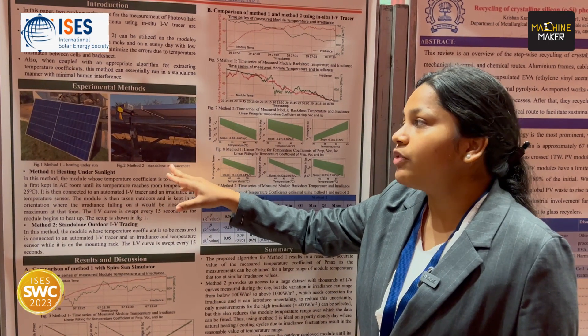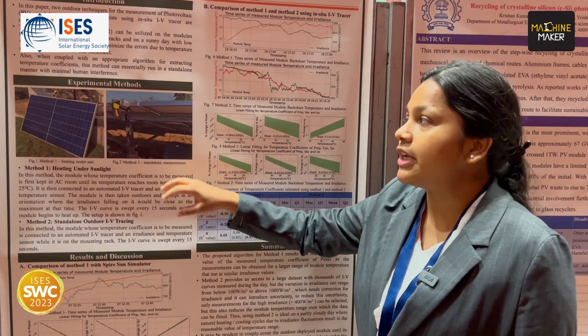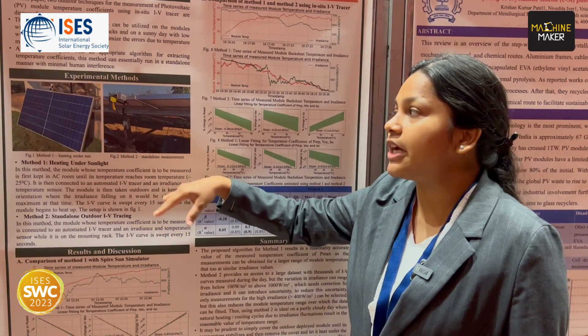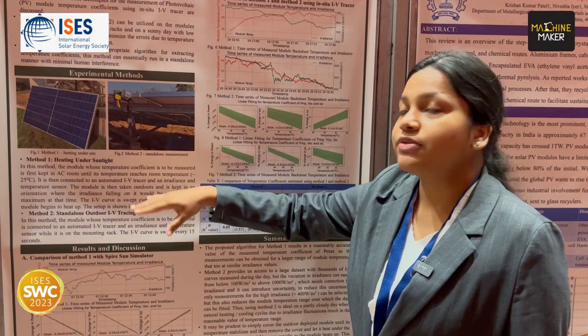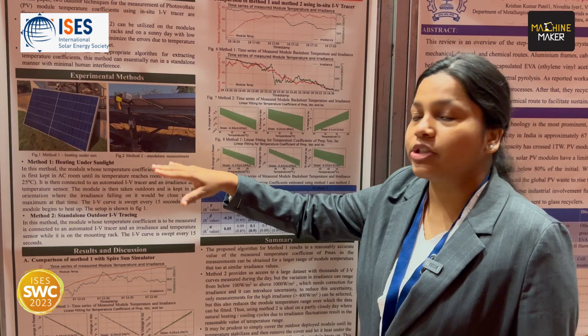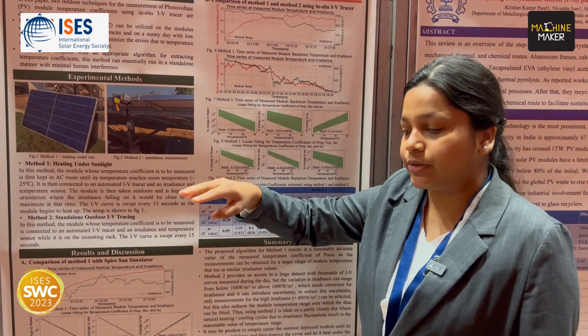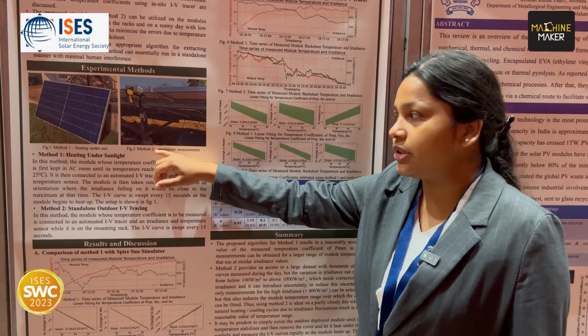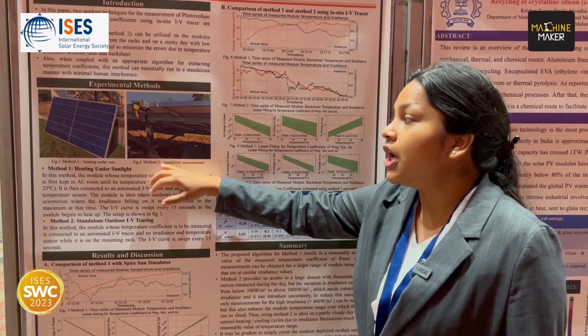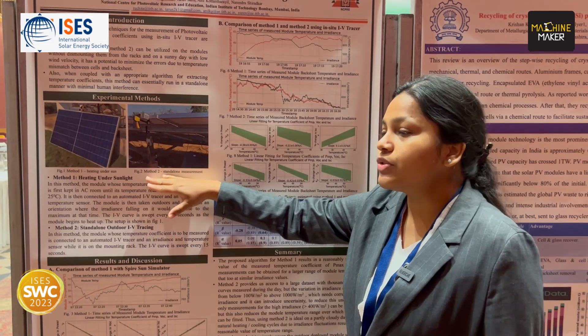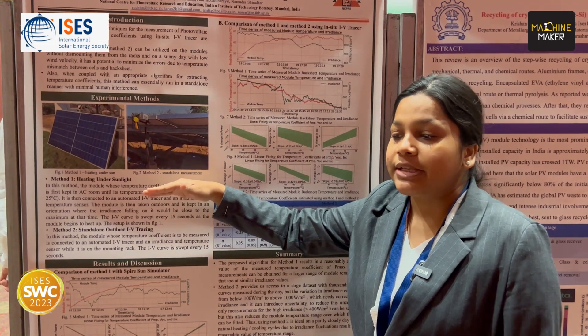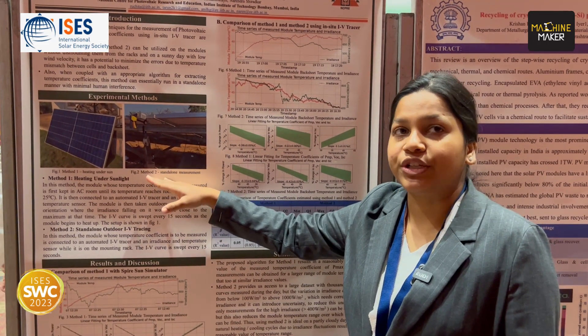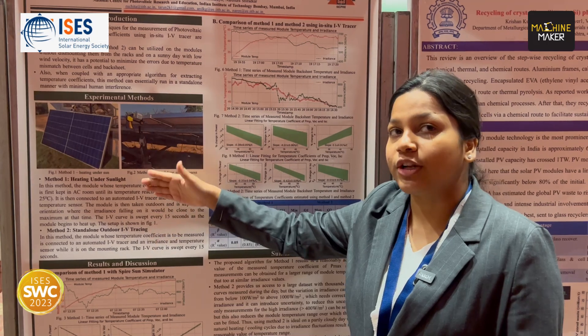In method 2, we have the module equipped on the PV array mounted as it is, and we are doing IV measurements for the whole day. Using those whole-day IV measurements, we can do temperature coefficient estimation. This can be useful if a plant owner wants to verify the temperature coefficients given by the manufacturer after installing the PV module.